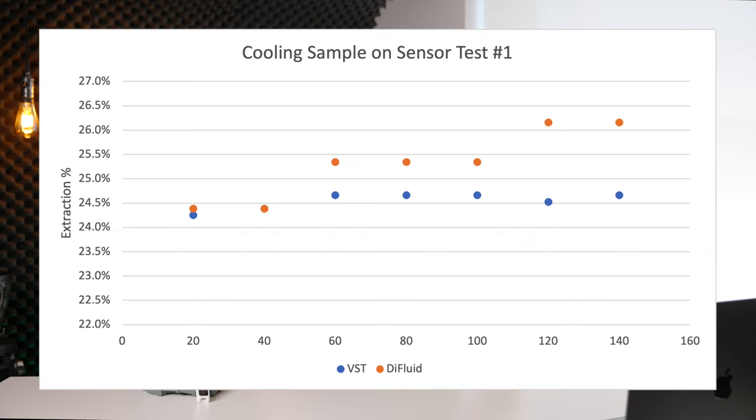Now, it's very important to note that this is not the correct way to use a refractometer, but I think it demonstrates where the Difluid falls behind. I put a warm sample on both of the sensors, and then I measured every 20 seconds as that sample cooled.